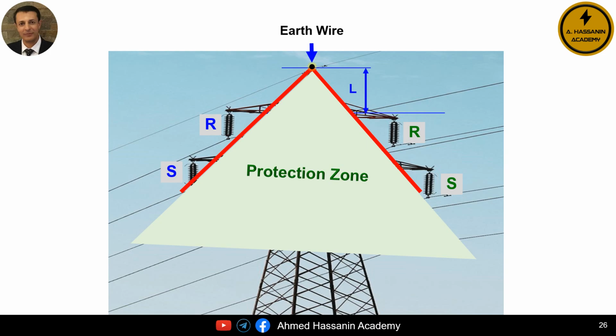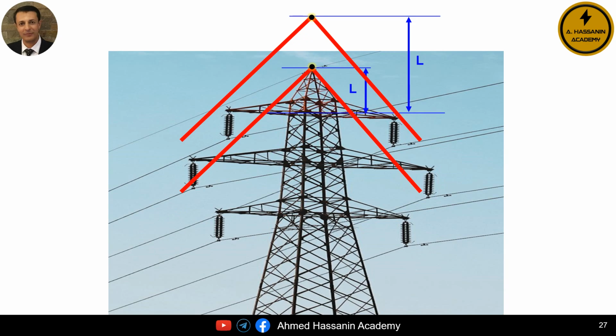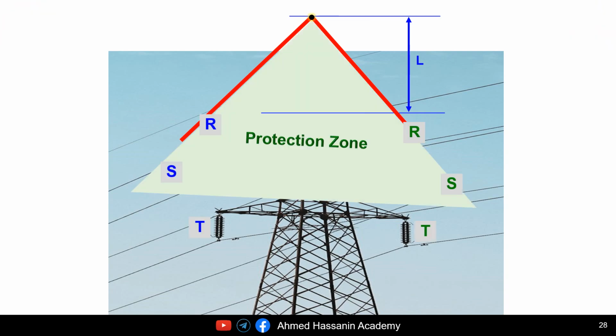So we want to know what is the solution to this problem. As long as we are constrained by the same protection angle, the solution is to raise the shield wire or earth wire or ground wire to a higher elevation than the previous height. This is necessary in order to achieve a protection angle or protection zone that is capable of covering or protecting all the insulators on the overhead transmission line. Indeed, by increasing the height of the shield wire or earth wire or ground wire, we were able to achieve a protection zone that successfully covers and protects all the insulators of the overhead transmission line.